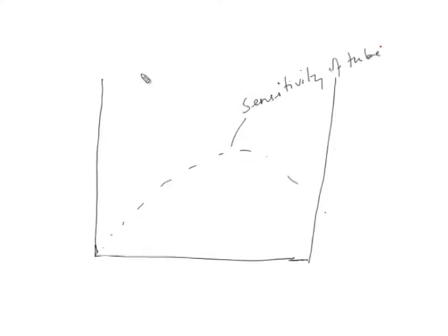Now, let us consider the energy transfer. A beta particle emitted from, say, 3H will excite the solvent, whichever solvent is present here, at a certain wavelength, say around 250 nanometers. You can see this is not really in the sensitivity zone of the tube.